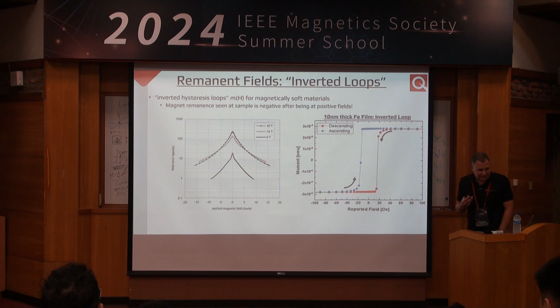So a very easy way we can solve this is simply to measure the palladium reference sample that we provide with all of these systems. You measure this palladium reference sample, which is an ideal paramagnetic sample, using the same sequence that you'll use for your sample, except for the temperature. We want to measure at 298 Kelvin because we know the susceptibility of the palladium reference sample very well at this temperature. So that's shown here. So, moment versus field, ascending and descending branches. From way out here, it looks okay. It's a straight line. It's a paramagnet. But zooming in, we see hysteresis here. That's not real. That's an instrument artifact. And we see the same sort of inverted loop where the descending branch crosses here, the ascending branch crosses here. But we know it should go right through the origin, both of them.